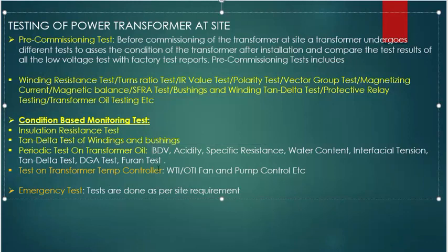Tests on the transformer temperature controllers such as the WTI and OTI, fan and pump control, etc., are also done as part of the transformer condition based monitoring testing. Also, emergency testing of the transformer is done on site as per the condition that arises on site.